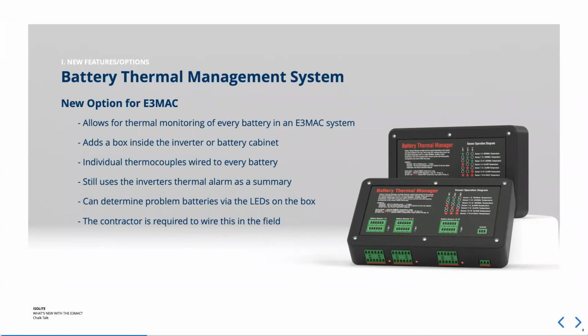It still uses the existing thermal alarm as the summarization, so you'll still get one thermal alarm, but now it's coupled more directly to each individual battery. This is something the contractor will have to wire in the field. We've made that pretty easy, though there are a lot of wires so it will take some time — but it's not too bad, since they have to wire the bus bars anyway. It just adds a little wire whip they dress up back to this system.